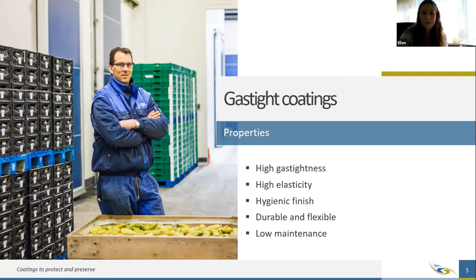This means the cold rooms are easily kept in regime. For example, during controlled atmosphere storage, the nitrogen generator uses a lot of energy while trying to maintain the same conditions. It's not desired for the fruit storage to leak, letting air enter so you cannot store your fruit completely.